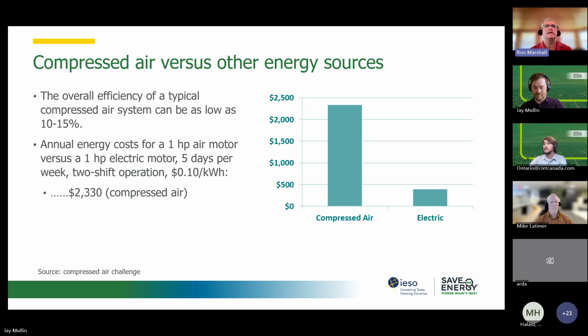And this is the air motor example again. Compressed air motor, and this is only 4,160 hours per year. A 1 horsepower air motor would cost $2,330 to operate, and electricity, if we advance, would be 390, right? A direct drive electrical power to that device. So pretty significant. It's only 4,160 hours. Very often end uses can operate 24/7, and the cost of that would be much higher than this, right? So it's an example of the savings. This is what blew me away when I started in this industry.